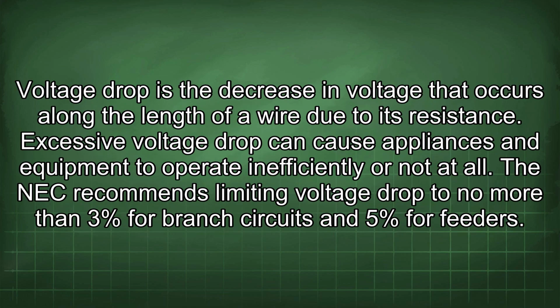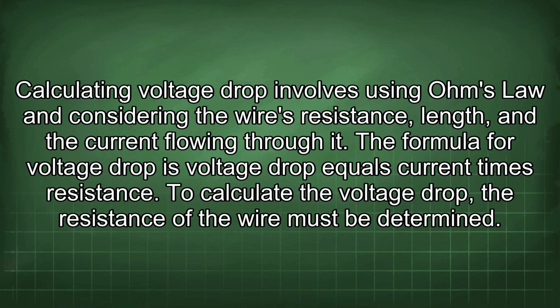Voltage drop is the decrease in voltage that occurs along the length of a wire due to its resistance. Excessive voltage drop can cause appliances and equipment to operate inefficiently or not at all. The NEC recommends limiting voltage drop to no more than 3% for branch circuits and 5% for feeders. Calculating voltage drop involves using Ohm's law and considering the wire's resistance, length, and the current flowing through it. The formula for voltage drop is voltage drop equals current times resistance.